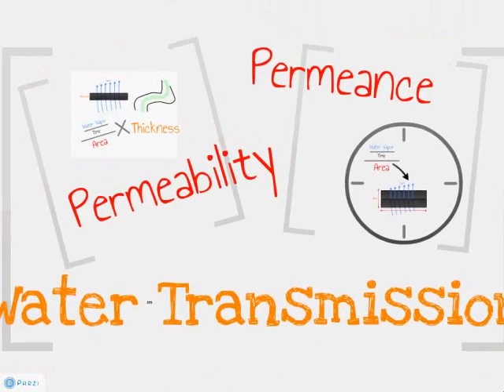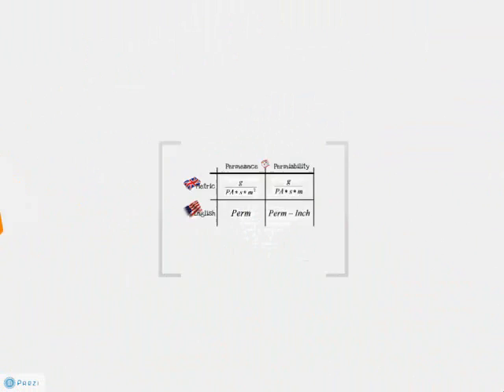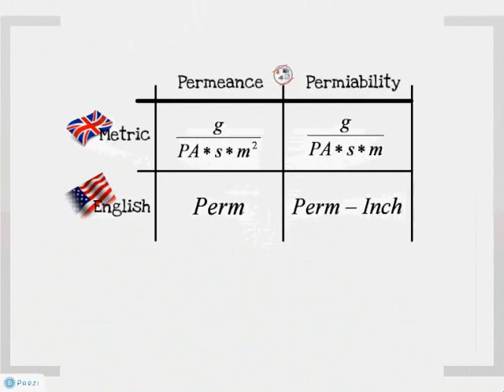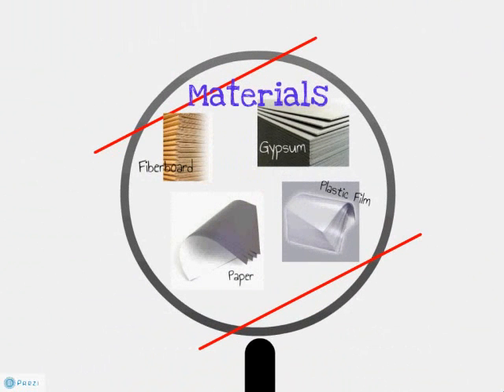Water vapor permeability is the arithmetic product of permeance and unit thickness, and has the units of perm inch or grams per pascal times seconds times meter. Permeance is used in performance evaluation, while permeability is a property of a material.